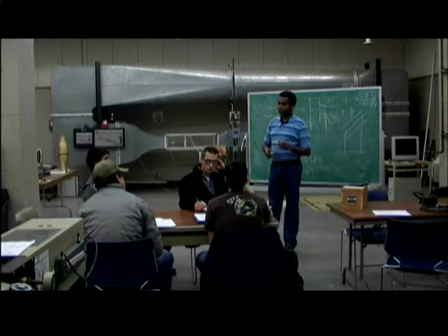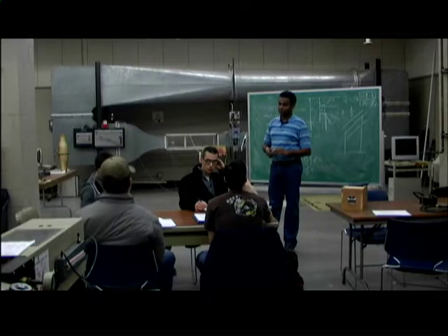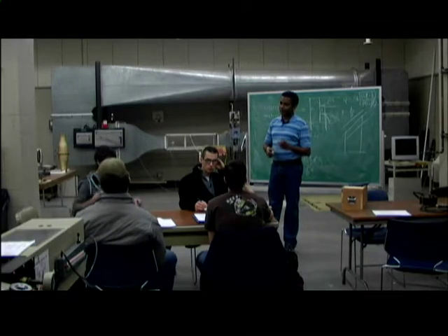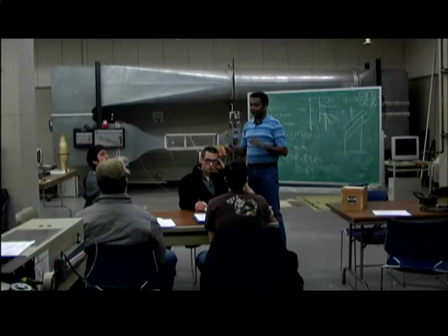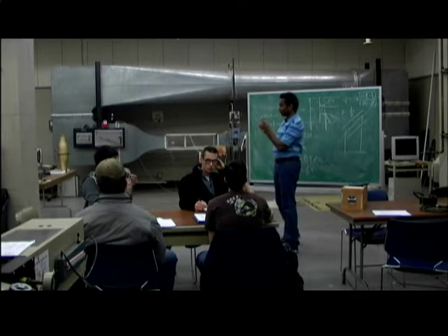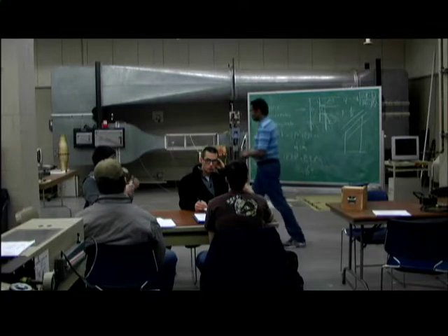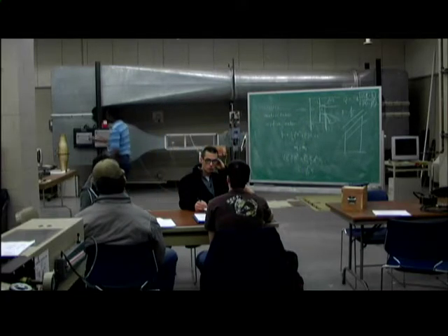So you think that it has a nominal flow rate? Yeah, like depending on how fast you turn it up, yeah. That's one possibility, a good one. But here we have a separate flow element. That's called a laminar flow element.